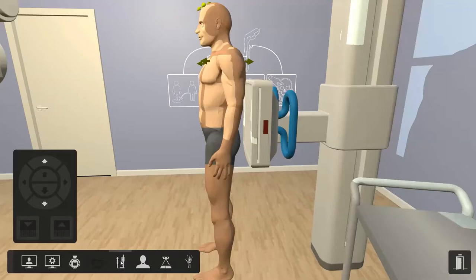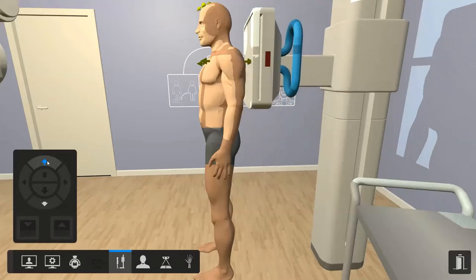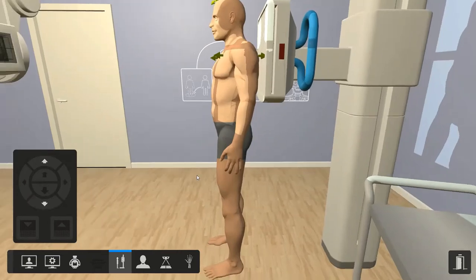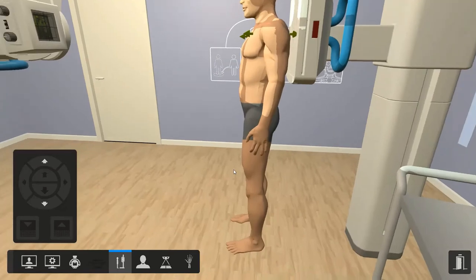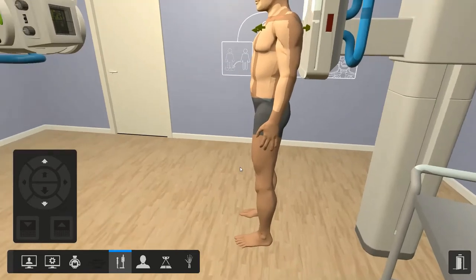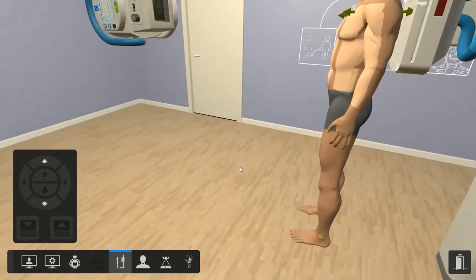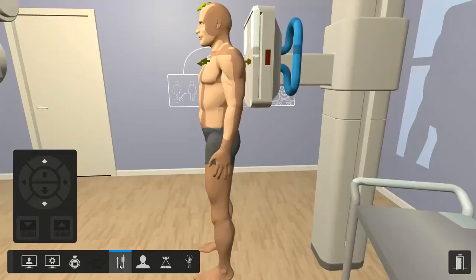There's the erect detector view, and you can move this up and down so you can check with the patient what position you want. I've deliberately moved that so we've got an unusual view — we're just sort of looking at the hips. At any point in time you can double-click on one of these icons and it'll take you back to the view that you should have.